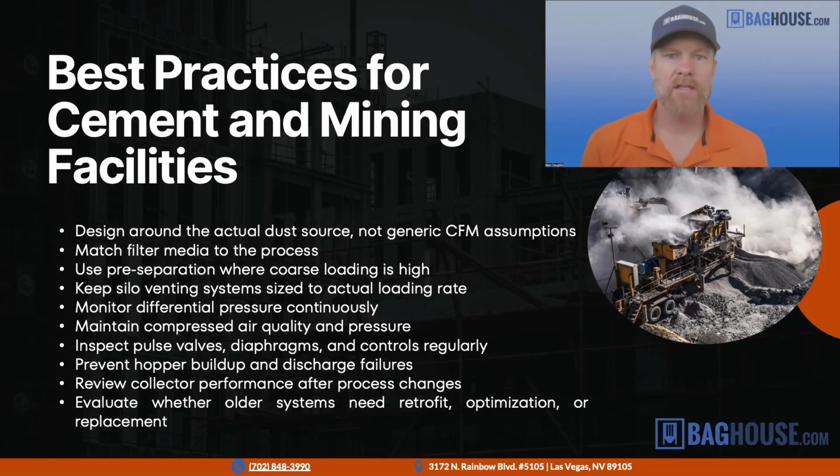So just to summarize from the presentation today, there are a few important points. Number one, the dust collection system should be designed around the actual dust source. It shouldn't be just a generic airflow number, CFM, and run with the dust collector. The reason is the hood design, the material behavior, the source dynamics at your particular part of the process are really important to making sure that the dust collection system performs as you expect it.